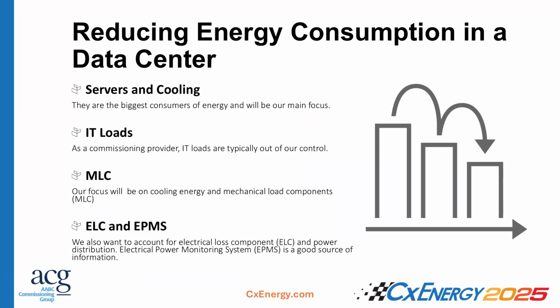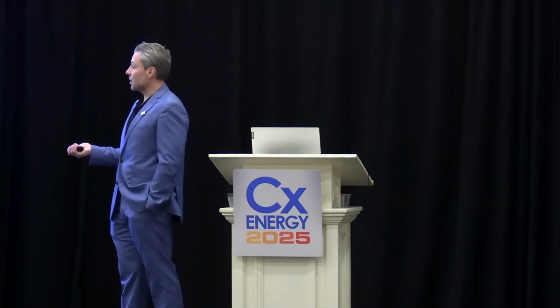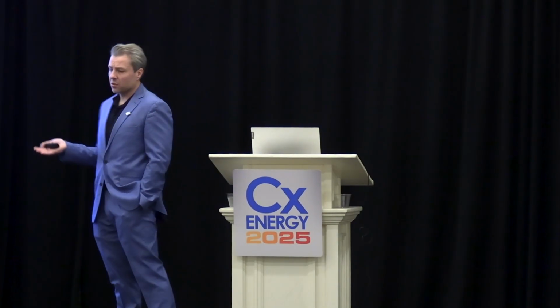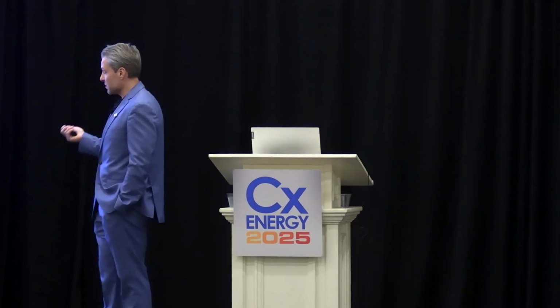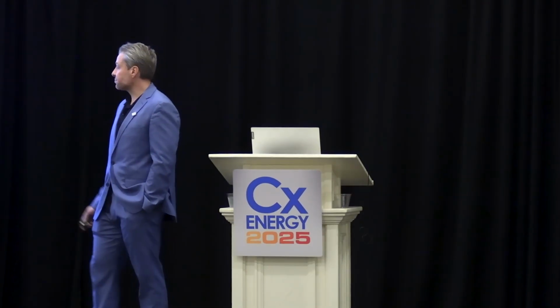MLC is the mechanical load component. This is becoming more of a focus with the latest ASHRAE standard, 90.4, the energy standard for data centers. So our focus as commissioning providers is going to be on cooling energy and mechanical load components. The ELC, the electrical loss component, also called electrical loss coefficient, covers power distribution in the data center. The EPMS system is a great source of information for power consumption and losses in the power system.